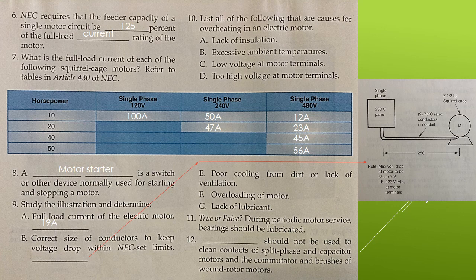For a 20 horsepower 240 volt, it would have a 47 full load amp current. For a 480 volt 10 horsepower, 12 full load amps. For a 20 horsepower, 23 full load amps. For a 40 horsepower, 45 full load amps, and for a 50 horsepower, 56 full load amps.